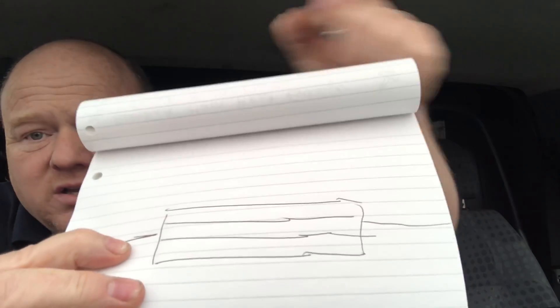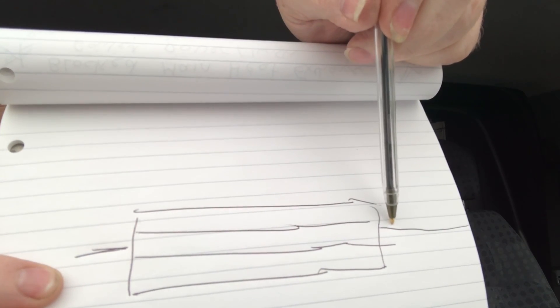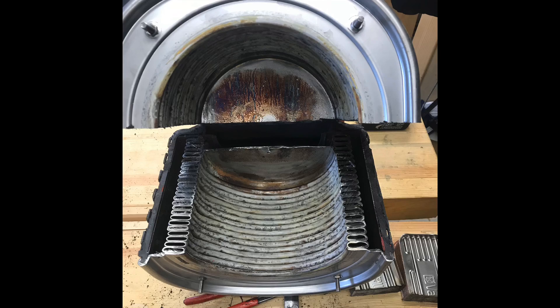If you imagine - I'll just draw on here - so we've got the flow going in, then you've got coils in the heat exchanger. My drawing is a bit shocking but if you imagine the flow goes into the heat exchanger there, and then it tees inside and goes around the coils in different sections. Then it comes out on the side as the return. So what it does is if part of it blocks, the rest of it can still be heating, but when it's on high it can start to boil in the heat exchanger because part of it's not getting any flow.